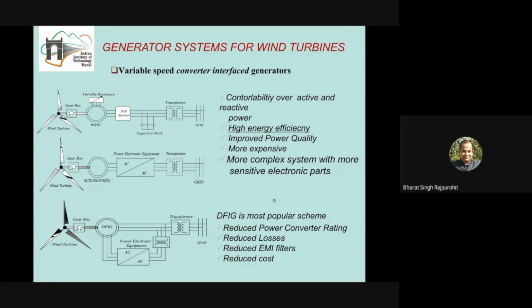Now coming to the permanent magnet synchronous generator, the cost of the PMSG is higher as compared to the DFIG because they are using a permanent magnet. Otherwise they are also very fine. They don't need any reactive power supply from outside, and they will be able to provide reactive power also. So when we are talking about PMSG or DFIG, the major role comes from either economics or grid stability. So there is a trade-off. Some of the companies, like Repower, are making PMSG, while GE and Suzlon are working on the DFIG.